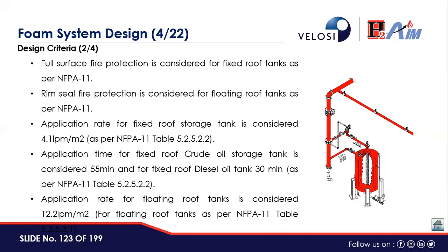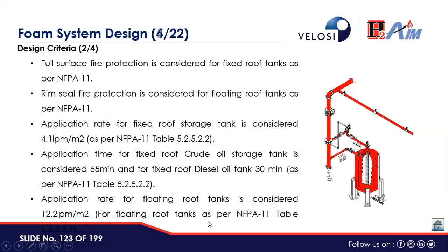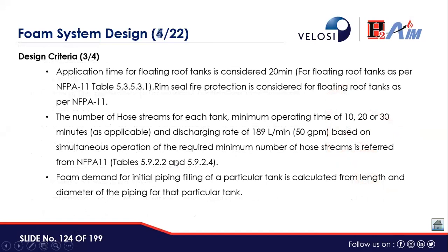5.2.5.2.2. The application time for the fixed roof crude oil storage tank is considered as 55 minutes and for the fixed roof diesel oil tank as 30 minutes. This is as per table 5.2.5.2.2 of NFPA 11. The application rate for the floating roof tank is considered as 12.2, and this is also as per table 5.3.5.3.1 of NFPA 11. The application time for the floating roof tank is considered as 20 minutes as per NFPA 11.